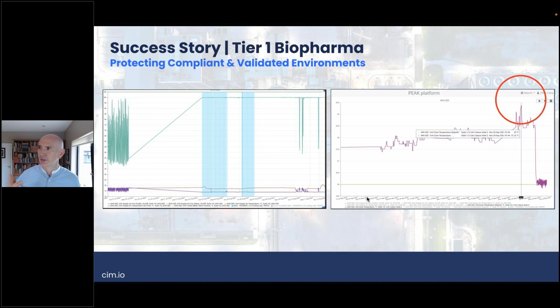Next one, I suppose, touches on the point raised previously around the manual overriding of set points. In this instance you can see, well, maybe you can't see it, but on the graph here we have supply air fans that are being locked at a specific hertz, even though they have VSDs installed, and that's essentially negating the job that the VSD does. So both of them are fixed at a manual set point, for no reason that we could understand anyway. Once the software picked it up, we were able to work with the on-site team to get those fans turned back into auto.